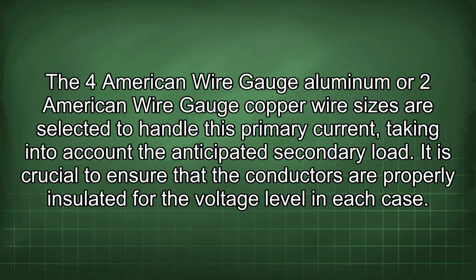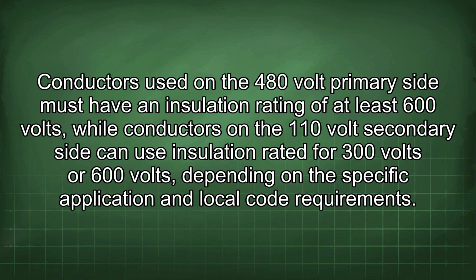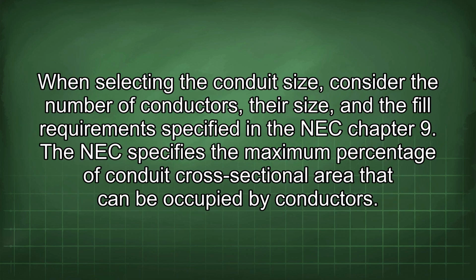It is crucial to ensure that the conductors are properly insulated for the voltage level in each case. Conductors used on the 480-volt primary side must have an insulation rating of at least 600 volts, while conductors on the 110-volt secondary side can use insulation rated for 300 volts or 600 volts, depending on the specific application and local code requirements. When selecting the conduit size, consider the number of conductors, their size, and the fill requirements specified in the NEC Chapter 9.